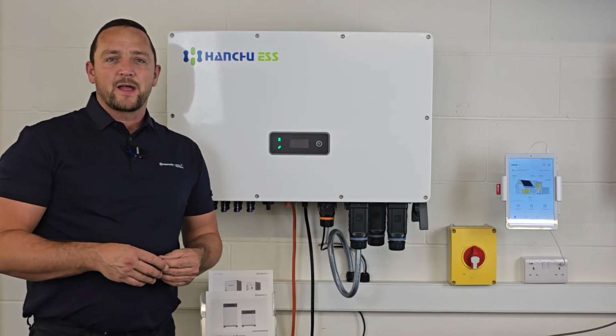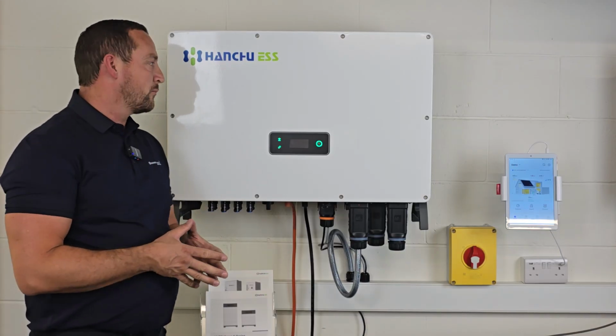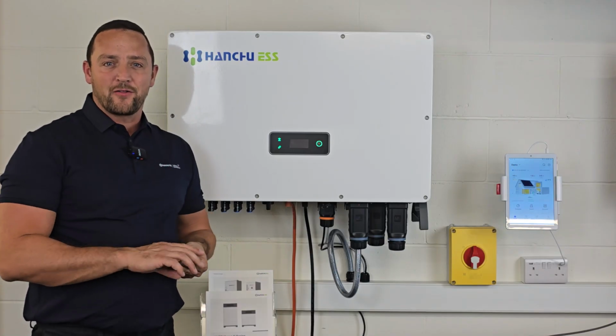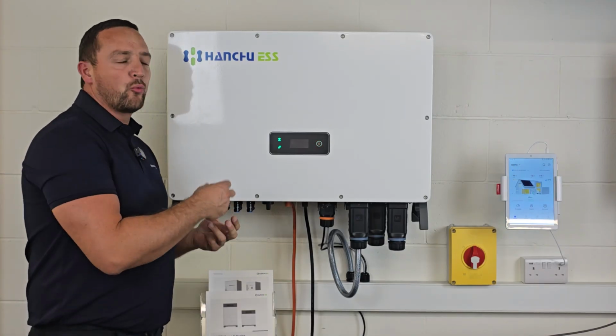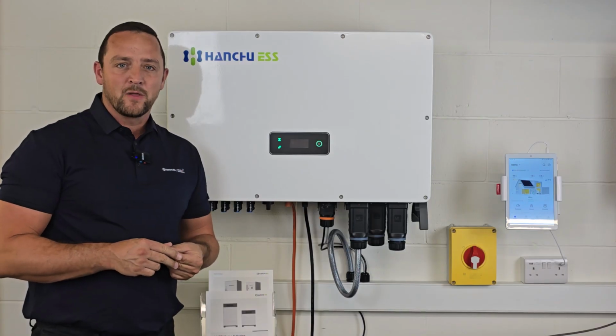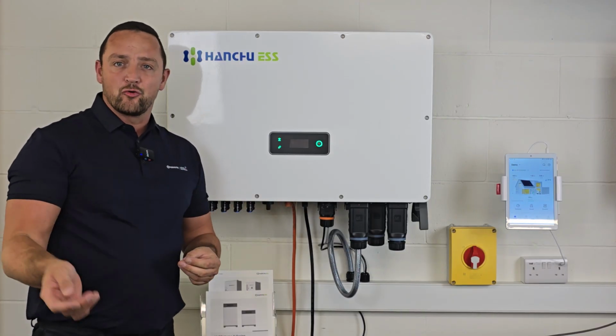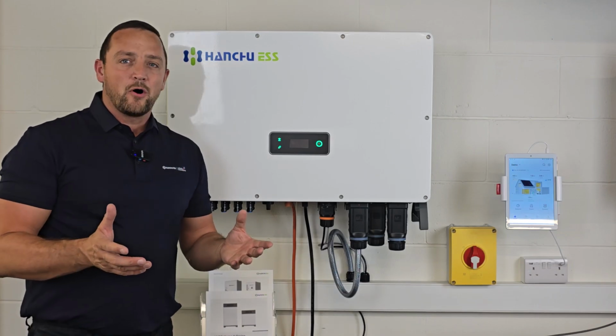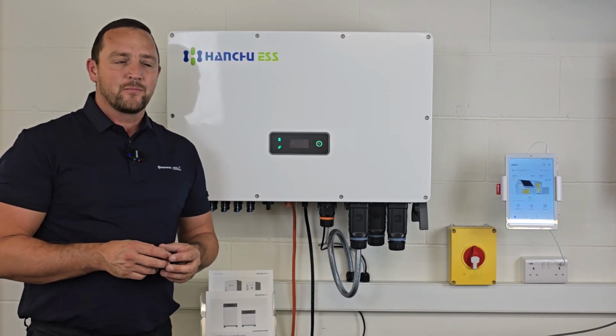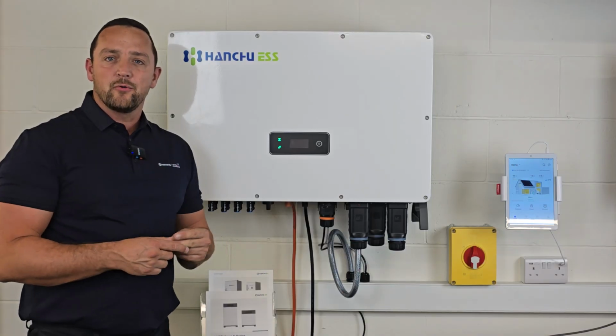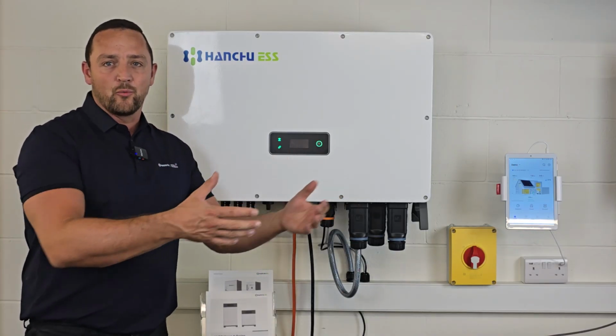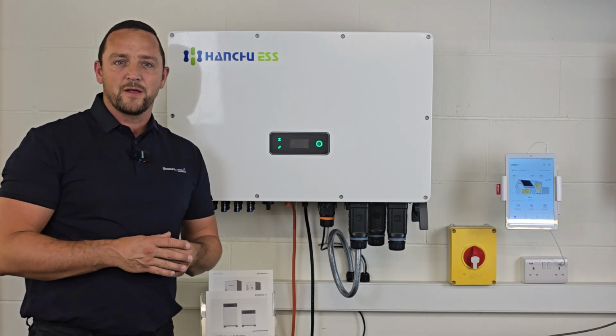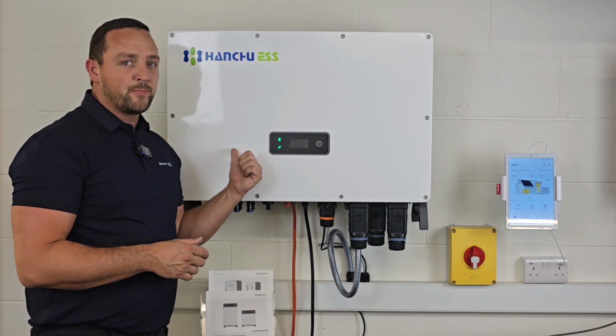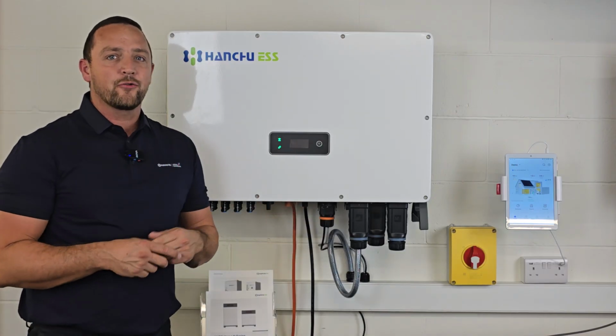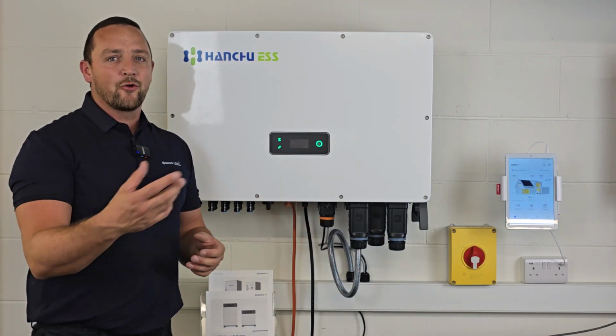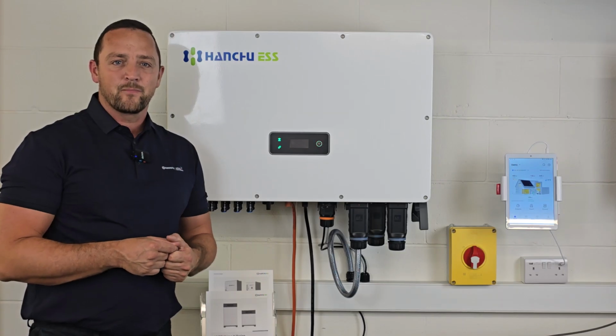So let's just very quickly recap this video. First of all, these are available in a 25, 36 and a 50 kilowatt unit, and you can put up to 1.5 times the PV input. We have an EPS which changes over in 20 milliseconds. We have a generator port for those off-grid applications. Each unit can be AC coupled, so you can use it as an AC retrofit where someone already has a PV system and an inverter in place. Parallel technology is built inside, which means we can put up to 4 in parallel, so we can increase that charge and discharge rate and also increase that PV input as well.